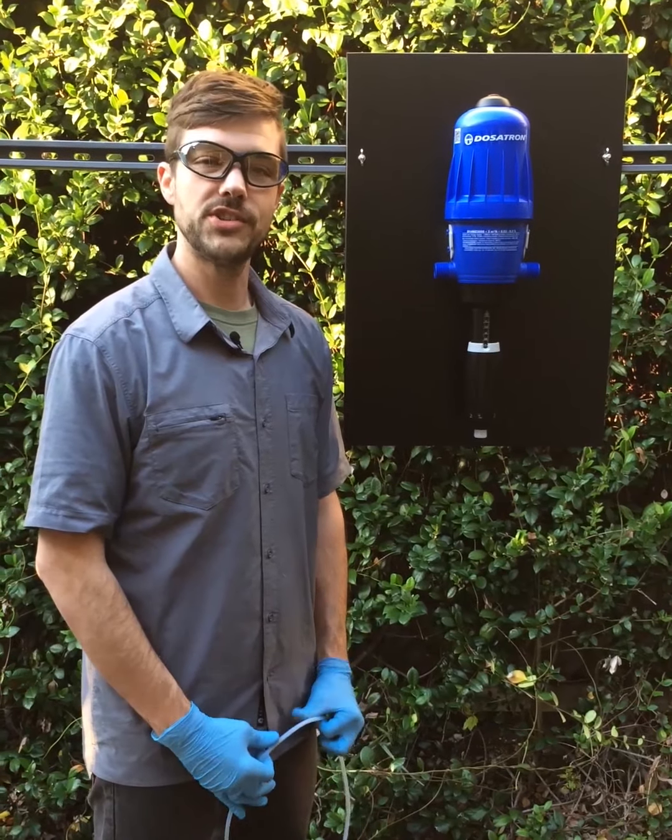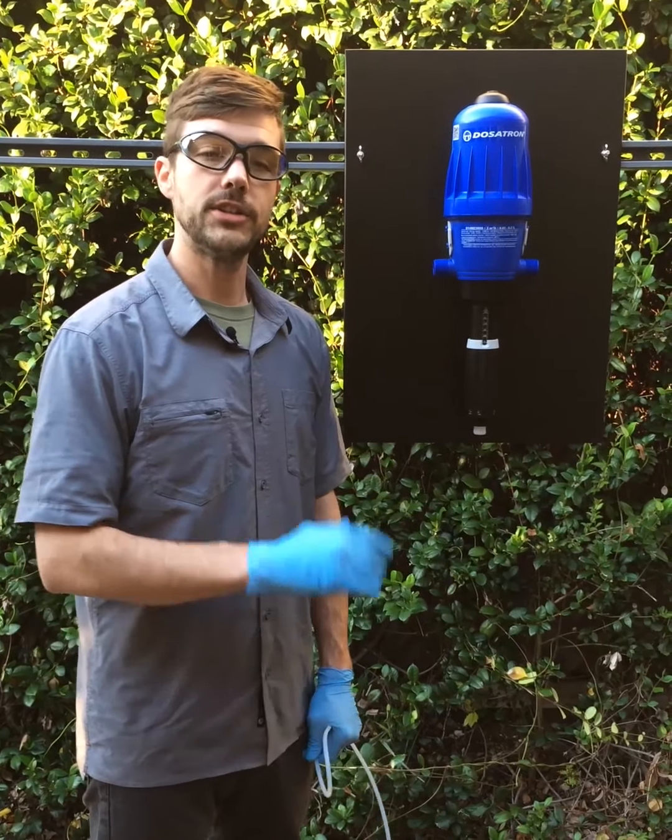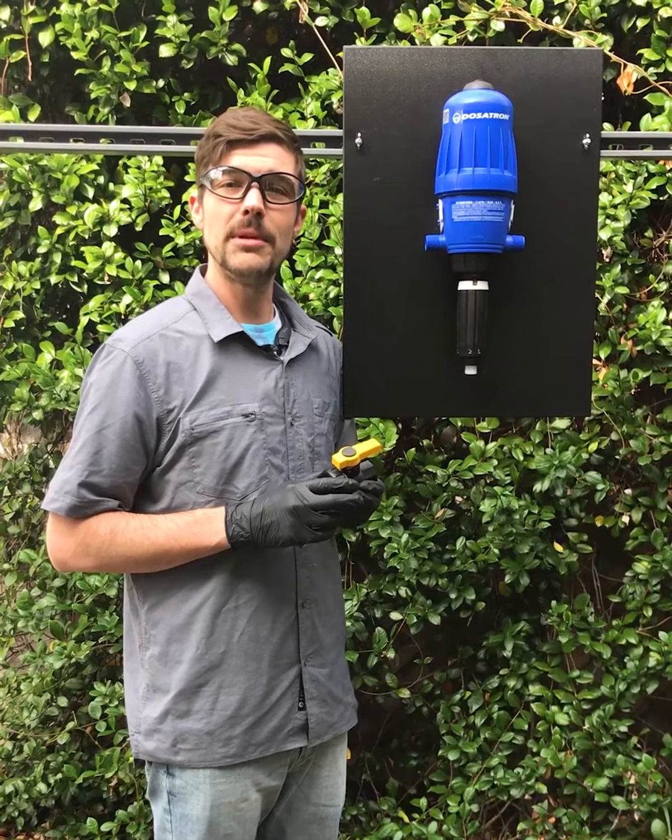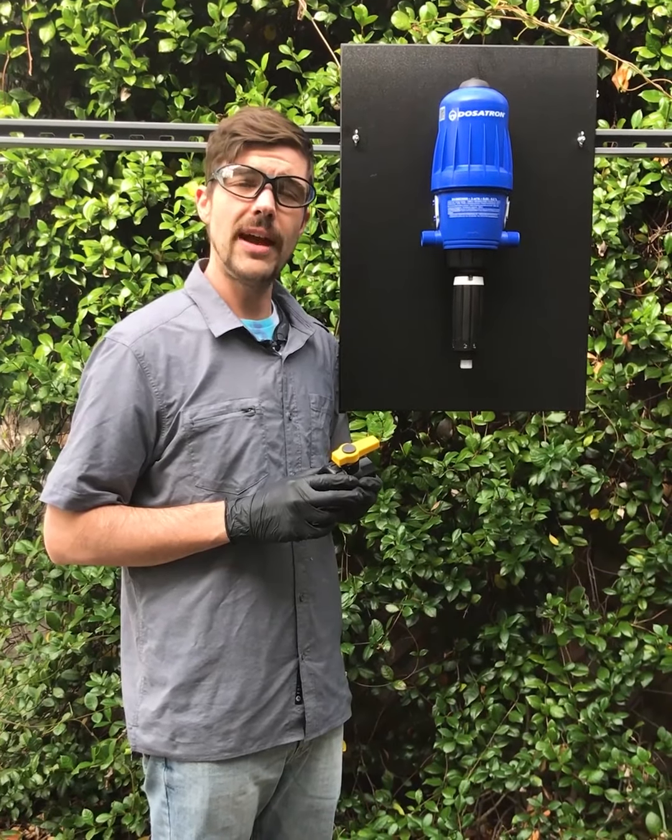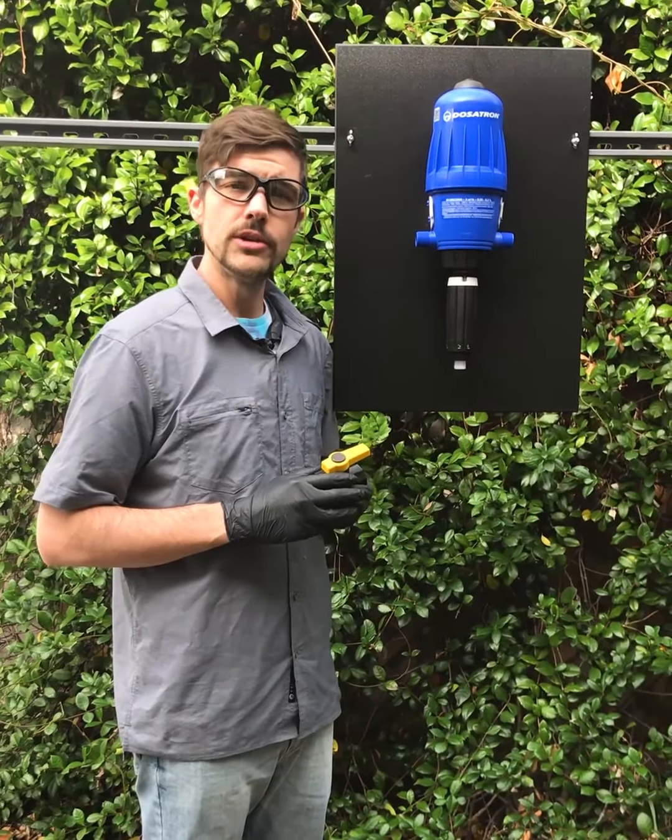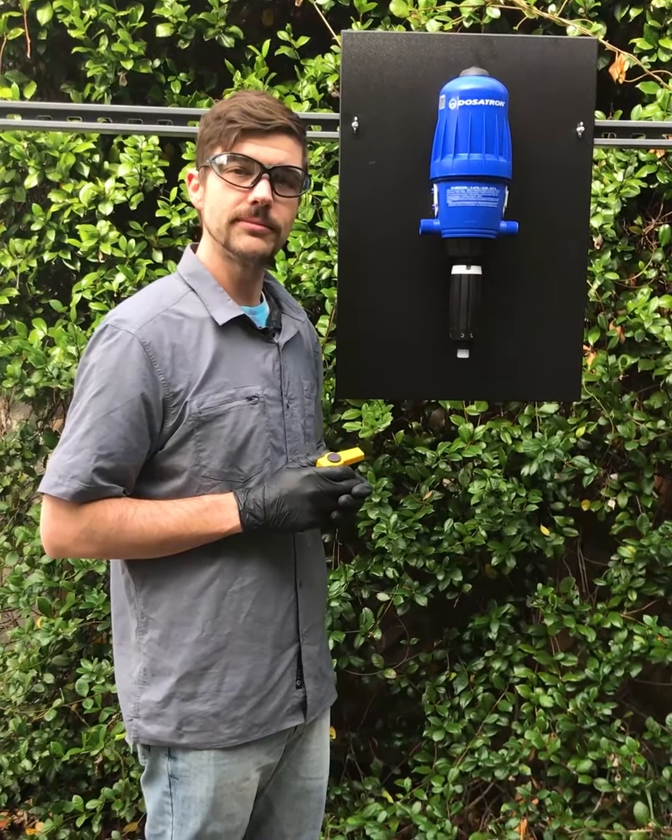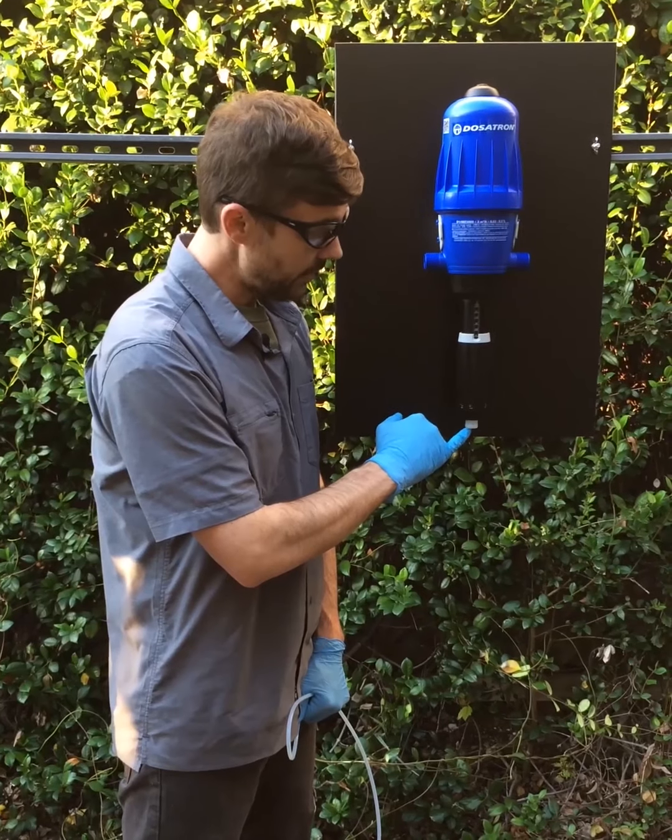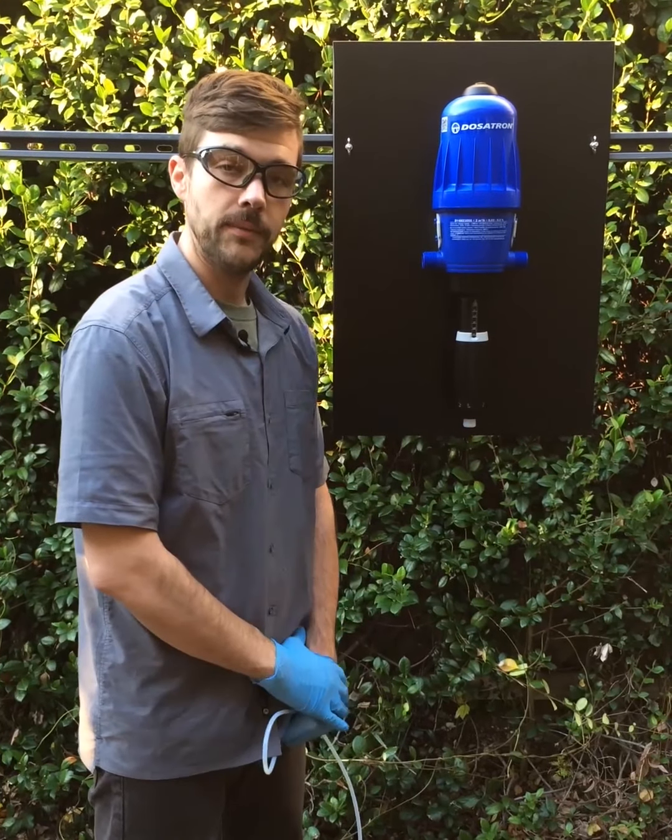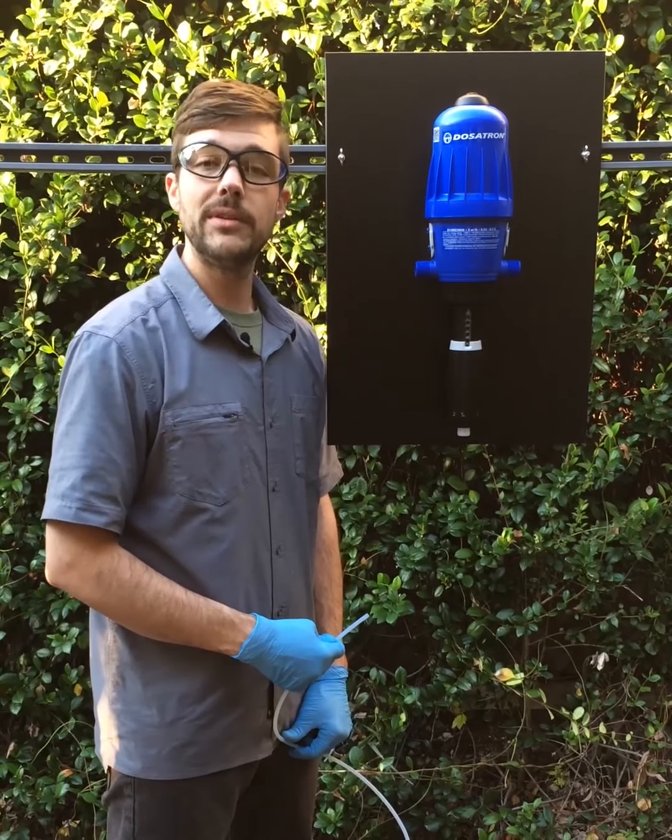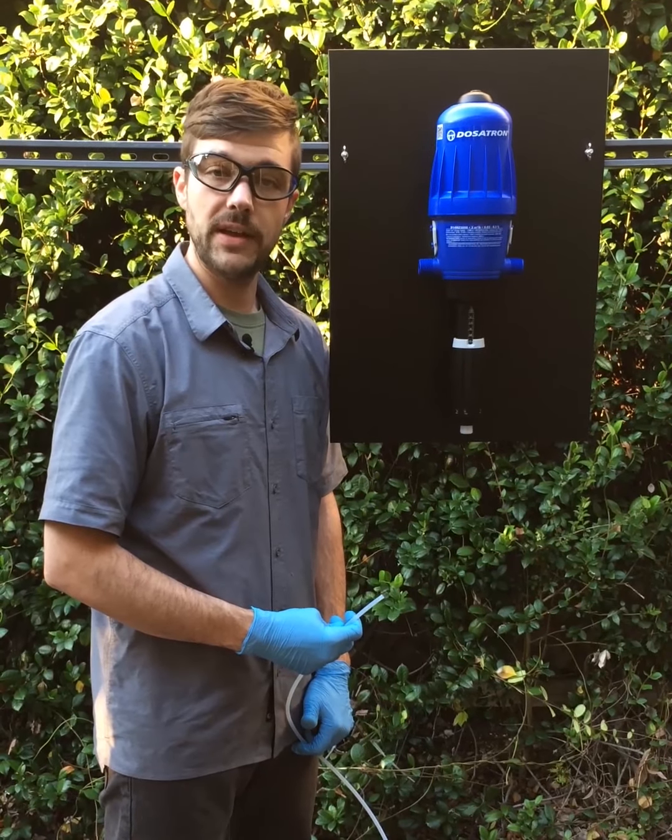Now that we've reinstalled our check valve, we want to go ahead and turn the unit on and let it run to check for any leaks. At this time, it may be beneficial to shut a valve downstream from the unit to apply back pressure on your system to help check for any drips or leaks. If you do notice any leaks coming from the check valve assembly down here, it is a good time to go ahead and replace it. Now that we've ensured that there is no leaks and the check valve is working, we're going to go ahead and reattach our hose assembly.